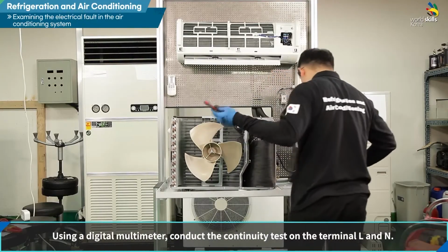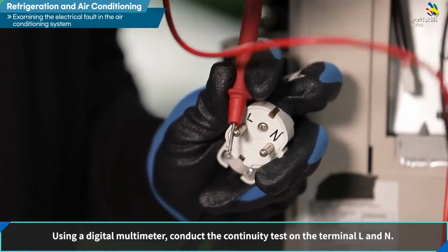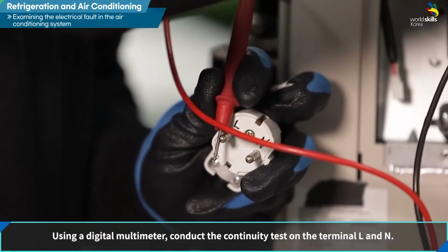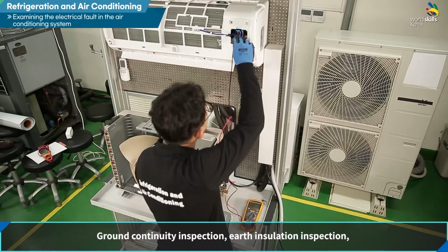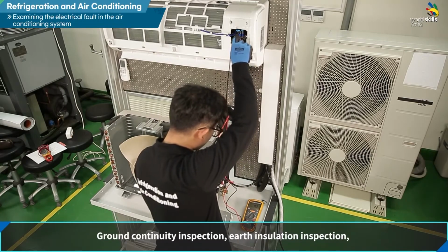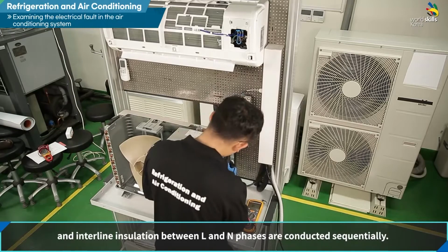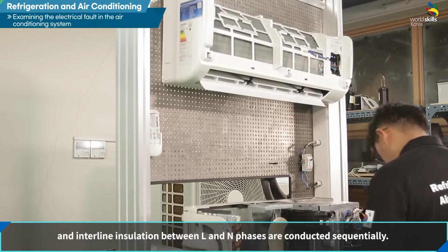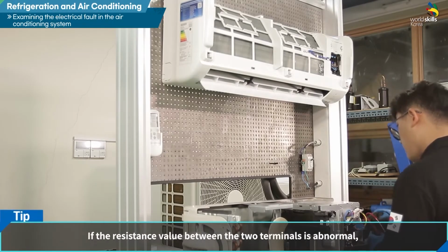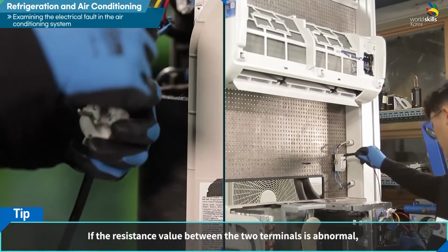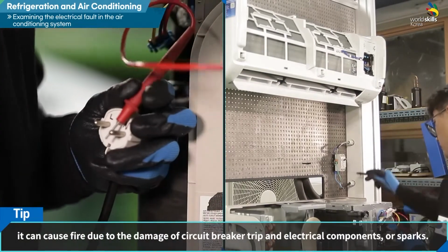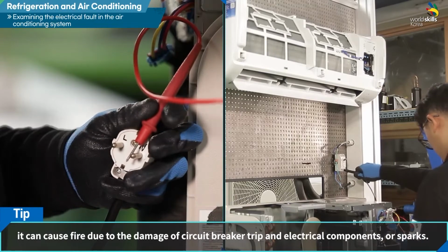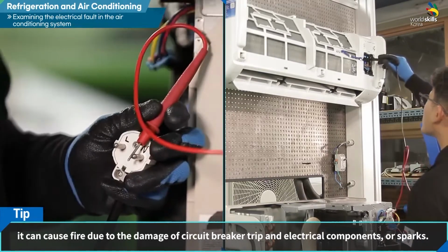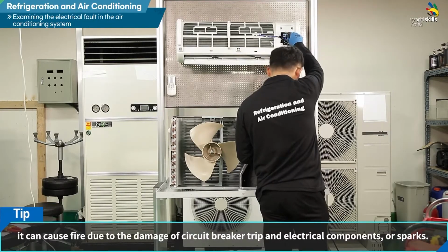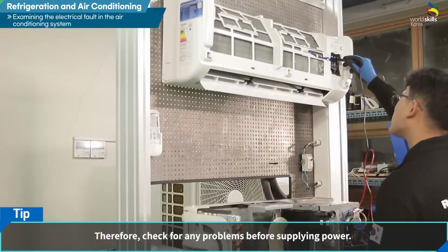Using a digital multimeter, conduct the continuity test on the terminals L and N. Ground continuity inspection, earth insulation inspection, and interline insulation inspection between the L and N phases are conducted sequentially. If the resistance value between the two terminals is abnormal, it can cause a fire due to circuit breaker trip, damage to electrical components, or sparks. Therefore, check for any problems before supplying power.